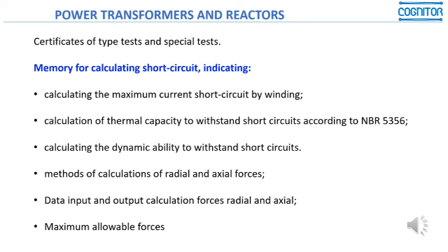It is interesting to mention that this is one exception caused by the size of the transformers, the weight they have, and the difficulty that we have to put this inside one lab. But putting this aside, the literature shows that something like 33% of the transformers that are tested for short circuits usually fail in the first test.